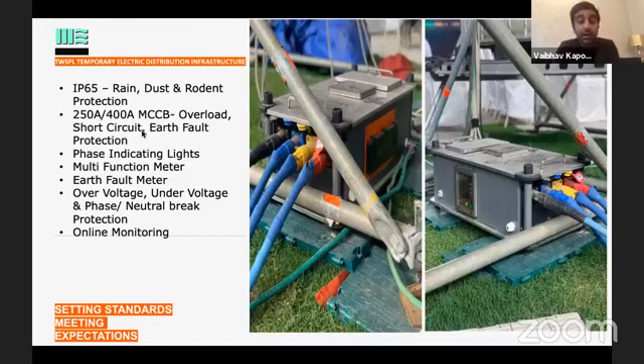Then come the earth fault meters on the back end side. In the other picture, there is a window. We've put earth fault meters inside this. So anytime an earth fault comes, we get the values. The acceptable value for an earth fault is 0 to 30 mA, milliamps. Anything above it, this system will automatically trip. So all the safeties are inside this box. If there is an earth fault, the MCB will trip. Then comes over voltage, under voltage. Again, it will automatically trip.